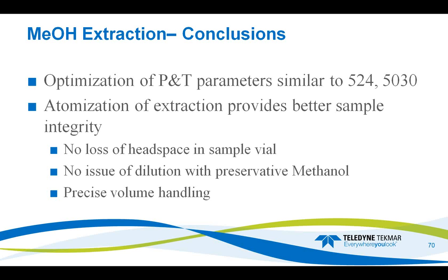Other benefits of using the Atomx is we have no loss of headspace in the sample vial because we never open it. We don't have to worry about the issues of dilution that are mentioned in the 5035 by adding your methanol preservative in the field. And we have precise volume handling because it's driven by a stepper motor with a syringe and it's automated.